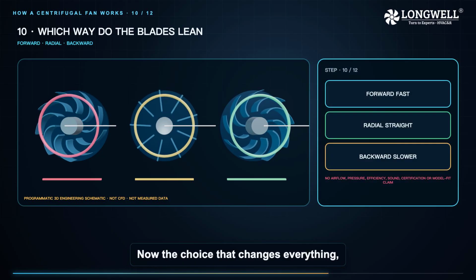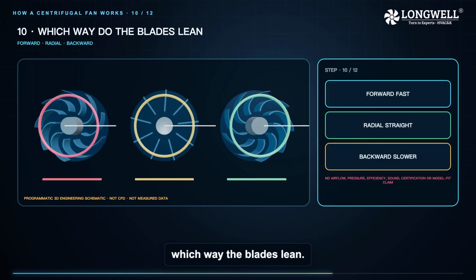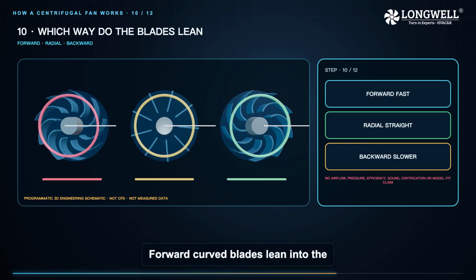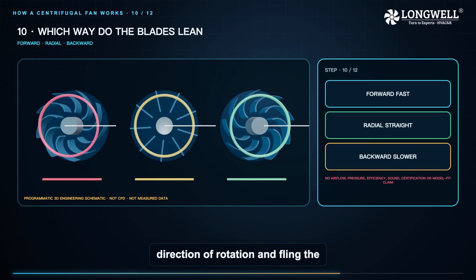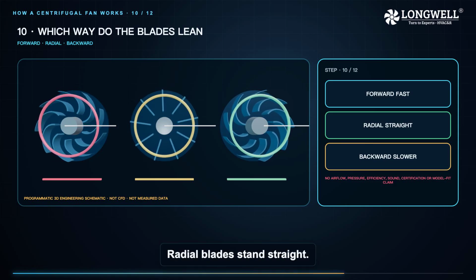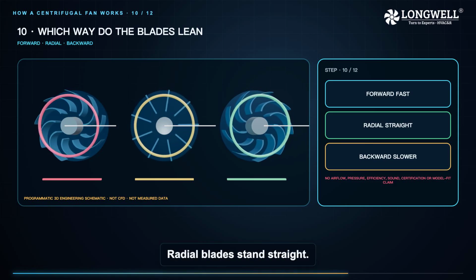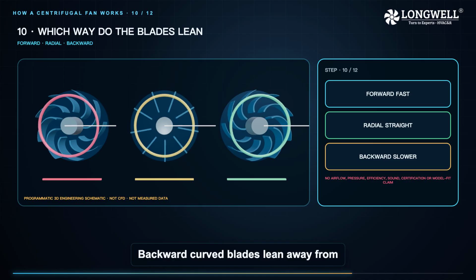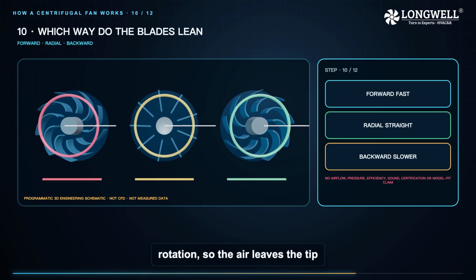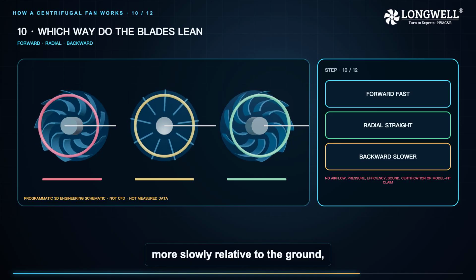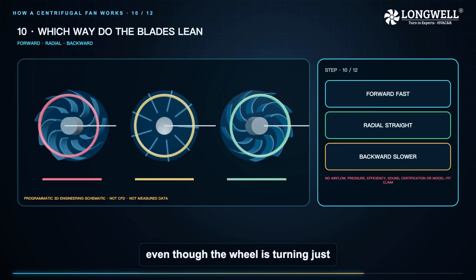Now the choice that changes everything: which way the blades lean. Forward curved blades lean into the direction of rotation and fling the air out fast. Radial blades stand straight. Backward curved blades lean away from rotation, so the air leaves the tip more slowly relative to the ground, even though the wheel is turning just as fast.